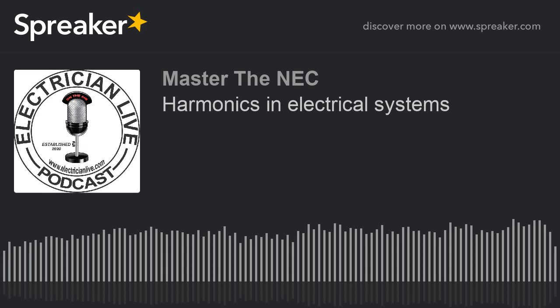So hopefully you got something out of that episode today where we talked a little bit about transformers and some of the things that you can do with harmonics and how you can alleviate it. And if you're ever lucky and you have a system that does not have harmonic distortion, then you're good to go. But if you're dealing with a single-phase system that's being derived from a three-phase four-wire system, or you have a four-wire three-phase system that's a Y secondary from a delta primary, and you have elevated harmonics, it can play a factor.